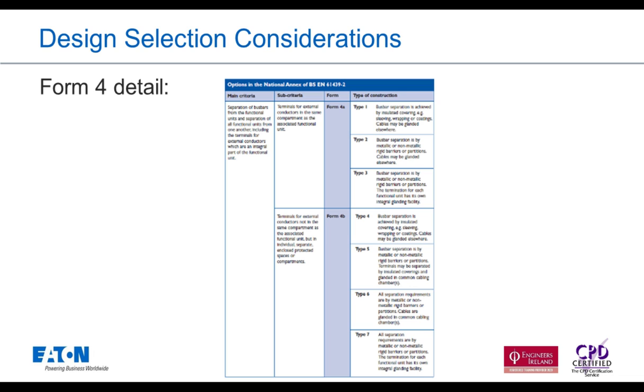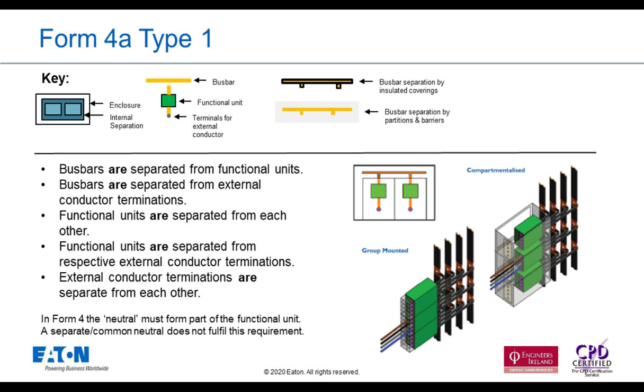Then we move on to Form 4. Form 4 is, I would say, a standard that's more in favour these days, definitely when it comes to switchgear assemblies, but even on some smaller distribution boards now, customers want that enhanced safety. So you're seeing this used more and more now. There are products in the market like MemShield 4, which is what I would call a typical wall-mounted power board, but it's got all the safety features of a switchboard in terms of the mechanical forms of separation.